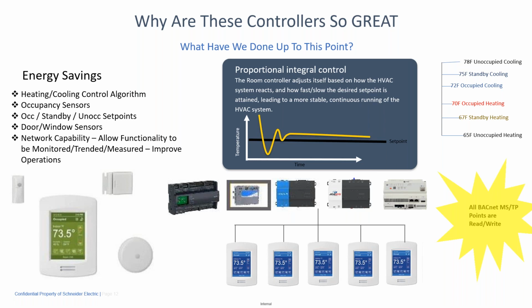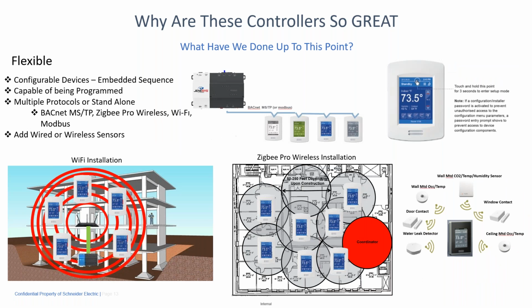You also have the capability to network these guys, right? You need to be able to measure what's going on, temperature value compared to the set point, and be able to make decisions based on that. So this is made as kind of a vendor agnostic type of device. BACnet MSTP, and then either Wi-Fi or Zigbee, and coming out of there goes BACnet IP to your supervisory device. So it doesn't matter if it's a Schneider AS, doesn't matter if it's a Johnson NAE, a Jenny, a Jace, a Trane SC, whatever the case might be. They're all BACnet MSTP devices that are all on the BTL site. They're listed and tested. All the points are readable and writable, so you have complete command over all those things to be able to do whatever you want from your supervisory device to control these in any manner you want. These are also super flexible controllers, right?